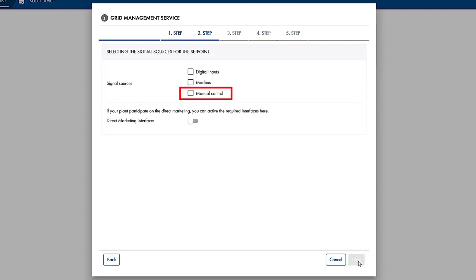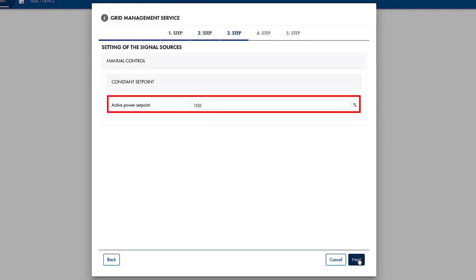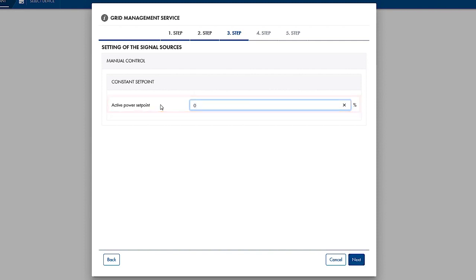Now select Manual Control as a signal source for the set point. Go to step 3 by clicking Next. For Zero Export, you have to set the active power set point to 0%. This will ensure that the inverters generate energy for self-consumption only, and do not feed any energy into the utility grid. Go to step 4 by clicking Next.